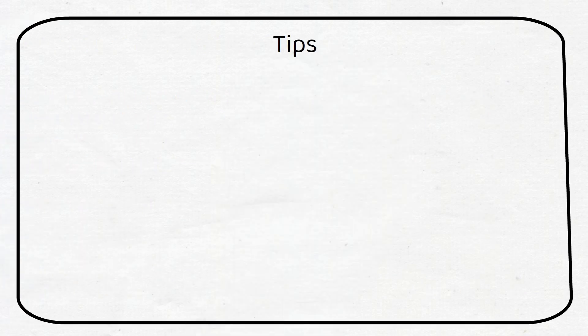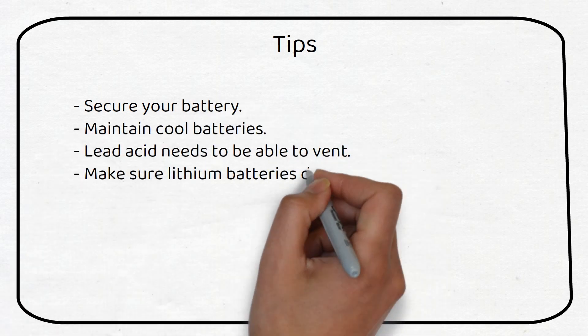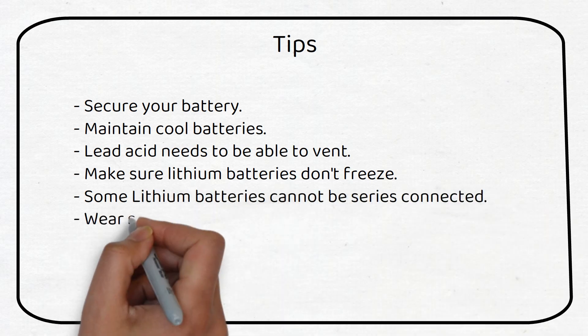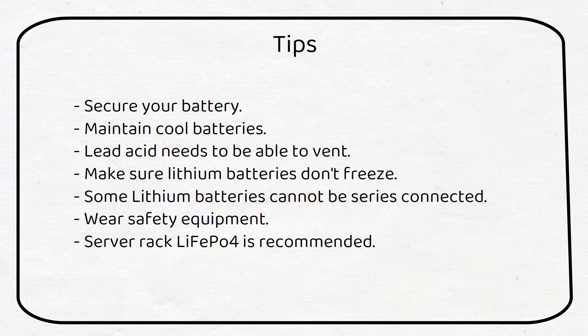If your battery bank is subject to vibrations, make sure it's mounted securely. Maintain cool battery temperatures to increase lifespan. Make sure lead acid batteries can be ventilated, even when it's sealed. Do not charge lithium batteries below freezing. It will damage the battery. Some lithium batteries cannot be connected in series. If you plan on doing so, make sure you get a battery that can. Wear safety equipment when wiring your batteries. Remove jewelry and use insulated tools.